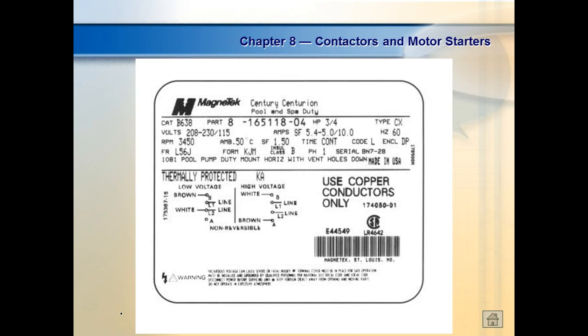Because of this. It's a 3/4 horsepower motor. 746 watts per horsepower. Right? You understand that. So the lower the voltage, the more current it's going to require to produce that horsepower. So what you got to do is get resistors out of your mind. If I've got a resistor out there and I lower the voltage to a resistor, then the current's going to go down. But we're not trying to deliver to a resistor. We're trying to deliver power to a load.